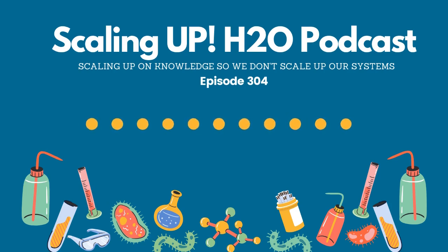So how long can you leave corrosion coupons in the system? Well, folks, you can leave them in as long as you want to. You just have to make sure that you know the original date that you put those in there, and we can run that calculation. Again, the longer that they are in there, the more indicative they're going to be of the system that you're trying to gauge the corrosion rates for. Now, typically, we'll see timelines of 30, 60, 90, 120, yearly coupons, things such as that. And when we're talking about corrosion coupons, and anything that we're trying to improve in a program, the more data sets that we have, the more opportunities we have to change the program.